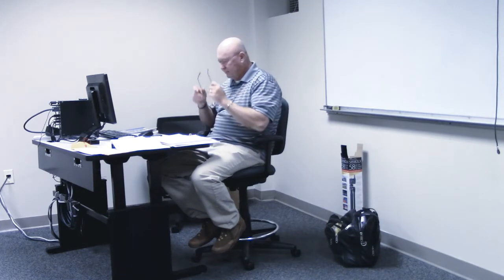And last but not least, number 20: as a secondary backup, at least one battery powered emergency lighting unit must be installed in every anesthetizing location per NEC 517.63.